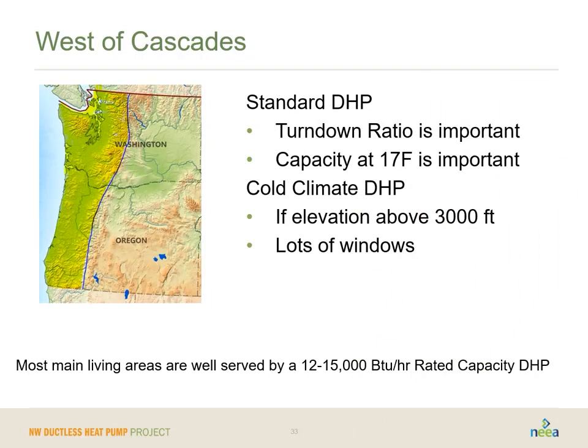I mentioned this earlier, west of the Cascades, turn down ratio is going to be really important, and the capacity of the equipment at around 17 degrees Fahrenheit is what you really want to look at. Make sure you're going to be able to get a good chunk of your load at 17 degrees. Again, if you've got an ungodly number of windows, or a very high elevation, meaning over 3,000 feet, maybe start thinking about a cold climate ductless heat pump. Most displacement scenarios here can get away with a 1 to 1.5 ton system, or a 12 to 15,000 BTU per hour rated capacity system.